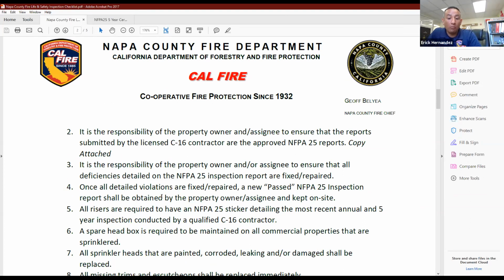There are proper forms for these types of inspections that I'll go over later, and I'll show you a blank copy. But we're not looking for invoices. There are actual documents that are required per California Fire Code. In addition to that, make sure that whoever is obtaining these documents is actually taking time to read what they receive, and take a look at the actual report.